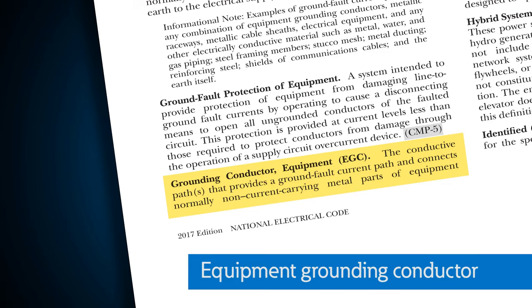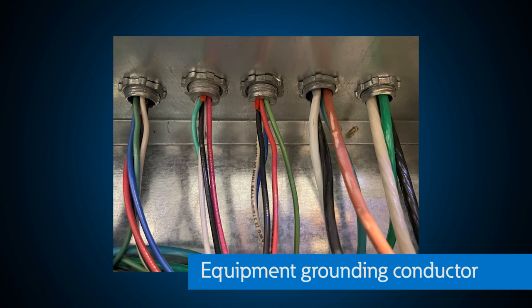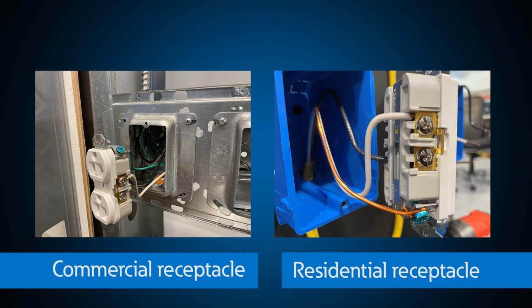The equipment grounding conductor is the conductive path that is part of an effective ground fault current path and connects metal parts of the equipment to the system neutral or grounded phase conductor — back at one location. Think of this as the bare copper conductor that you carry out to all of those loads; if you open up any receptacle, that bare copper conductor you see is your equipment grounding conductor. We want that to be low impedance and able to carry fault current should a ground fault occur in the system.